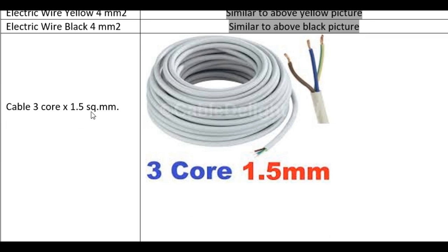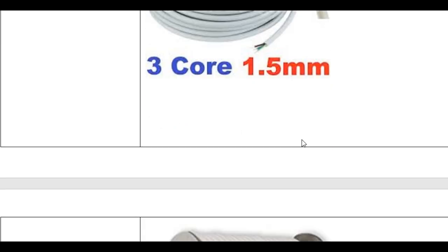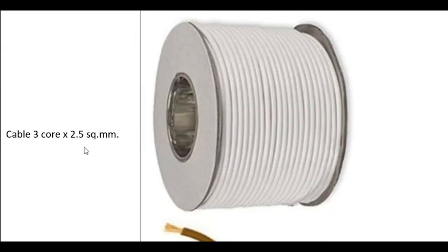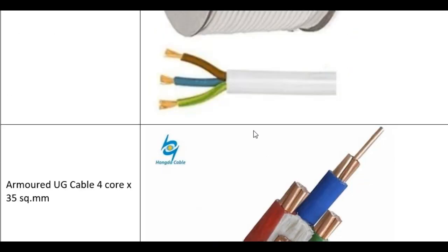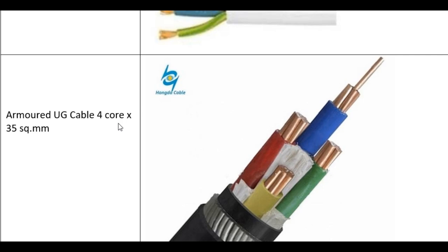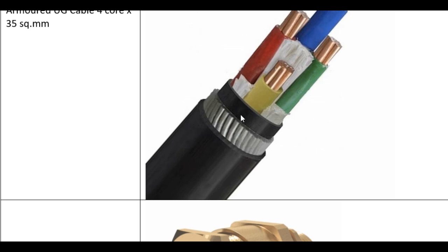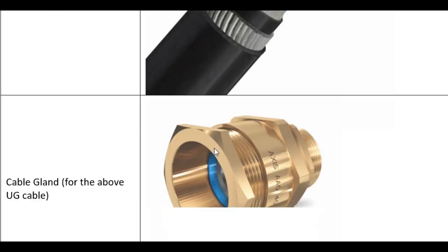Next is cable 3 core 1.5 square mm. 1.5 square mm 3 core cable is our lighting range of cables. These lighting cables are very flexible, can be used repeatedly for connecting various lighting fixtures, used in so many applications. Okay. Cable 3 core 2.5 square mm. Okay. And next is armored UG cable 4 core into 35 square mm. We use as main supplies and branch as well, depending upon the load conditions, load requirements.